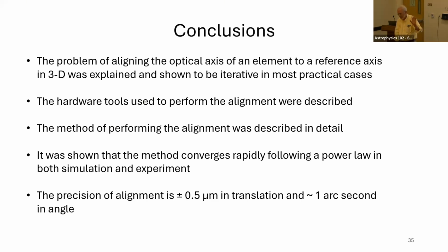Yeah, well, where I have said a couple tenths of a micron, it's with a 10x objective. And for my lab where I don't have vibration tables and all that, you can put a 100x objective on here. Any infinity corrected, non-cover glass type objective will work. So you've got that potential sensitivity.